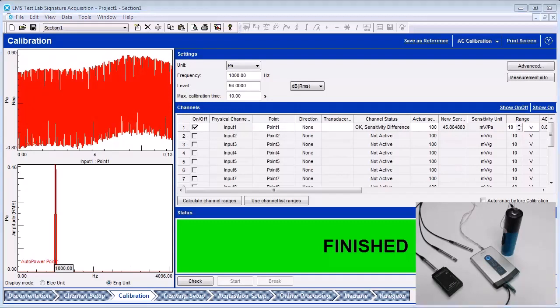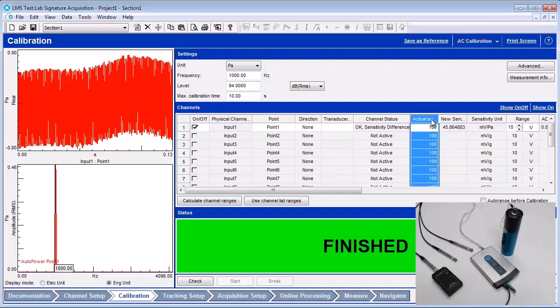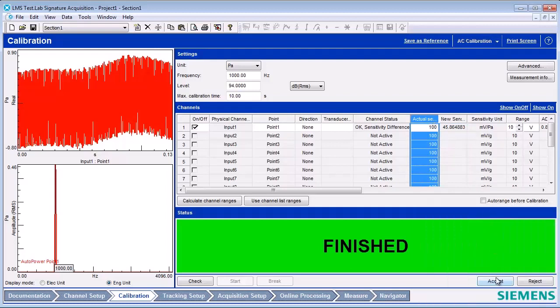The newly calculated calibration values are shown in a column called New Sensitivity. The previous calibration values are shown in the column labeled Actual Sensitivity. Press the accept button to update the calibration values.